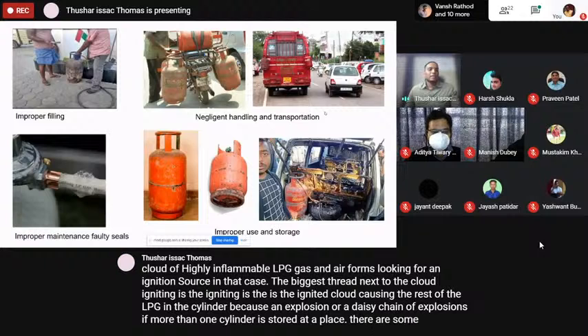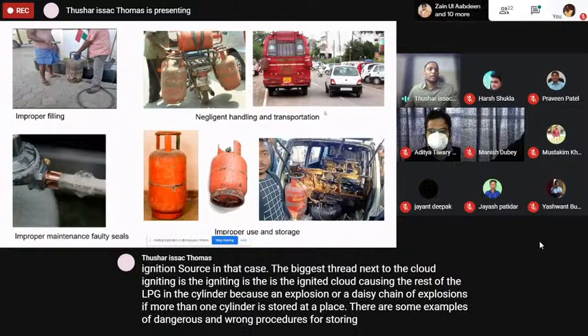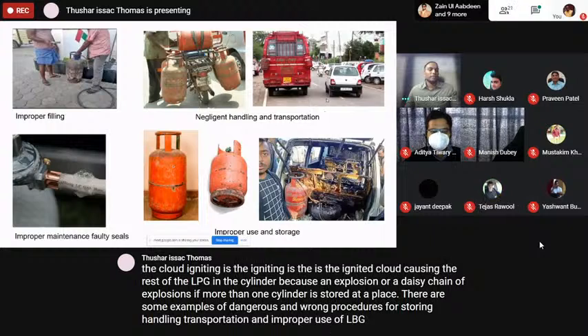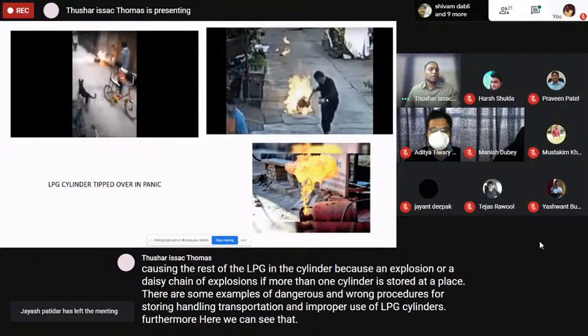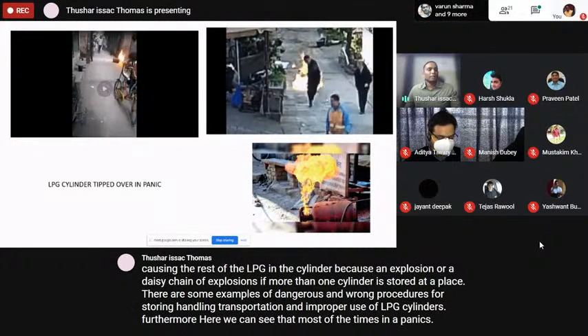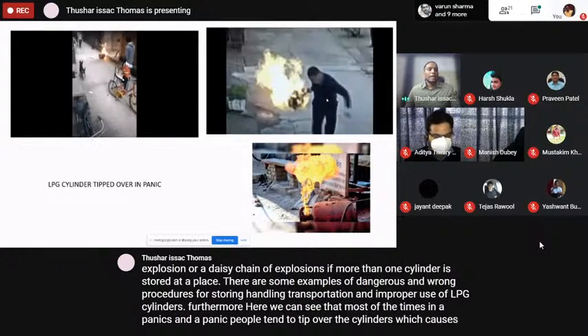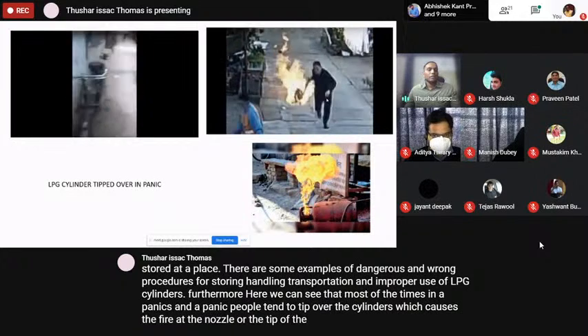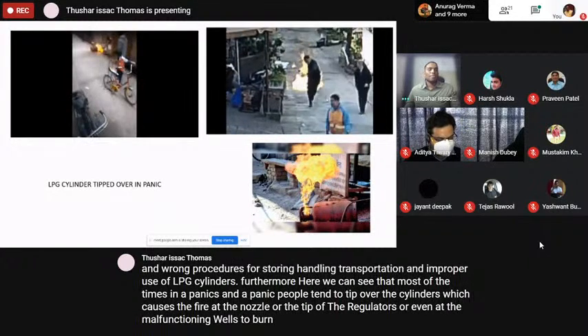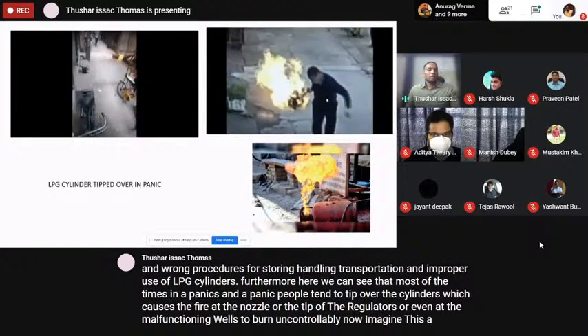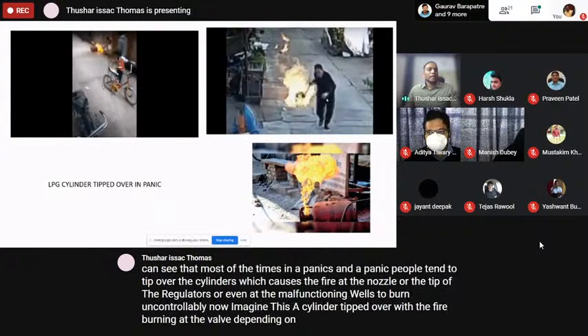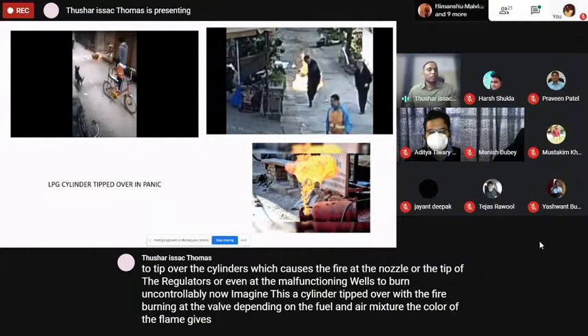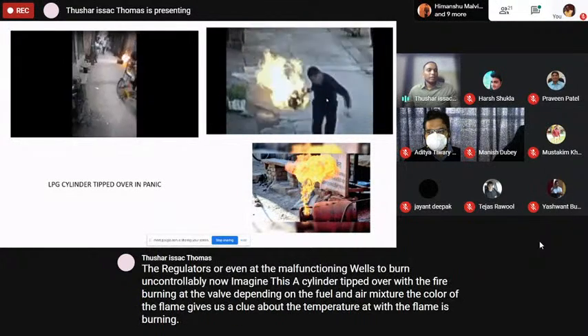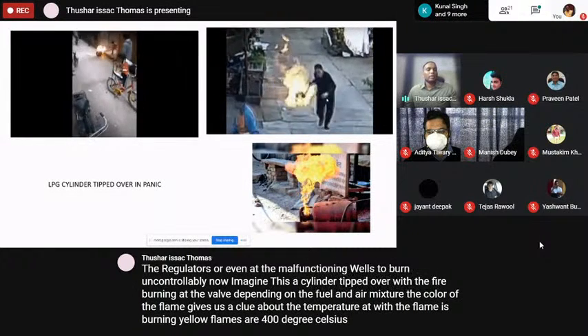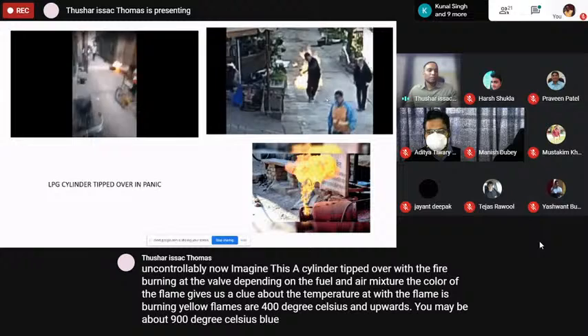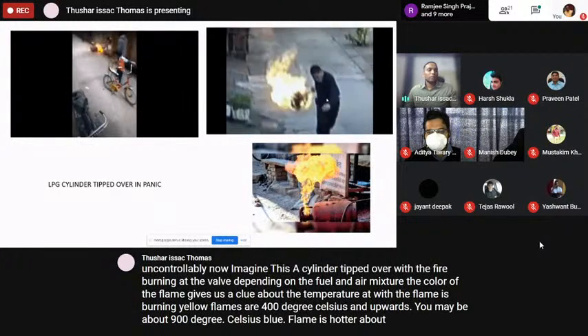There are some examples of dangerous and wrong procedures for storing, handling, transportation, and improper use of LPG cylinders. Furthermore, here we can see that most of the time, in a panic, people tend to tip over the cylinders, which causes the fire at the nozzle or the tip of the regulators, or even at the malfunctioning valves, to burn uncontrollably. Now imagine this: a cylinder tipped over with the fire burning at the valve. Depending on the fuel and air mixture, the color of the flame gives us a clue about the temperature at which the flame is burning. Yellow flames are 400 degrees Celsius and upwards to maybe about 900 degrees Celsius. A blue flame is hotter, about 1000 and upwards degrees Celsius.